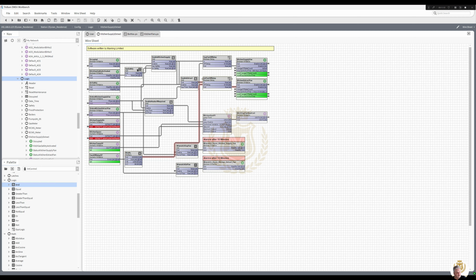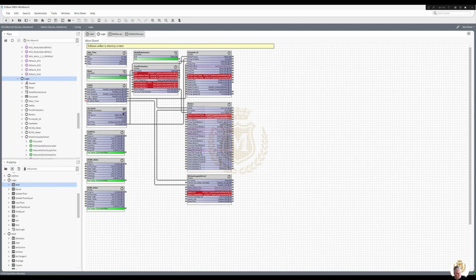I mean, if everything turns off, what will happen there is we've got a delay on the supply fan and a delay on the extract fan. So we'll turn everything off, which will, of course, make that enable go false. It will shut down the PI loop, shut down your heating coil, but we will still put air across the coil for 5 minutes. But it can be adjusted if they want to, but we will put air across so that we are not blowing up the coil or anything like that. We're still moving air across for 5 minutes after we've closed down the kitchen supply. That's a safety precaution.